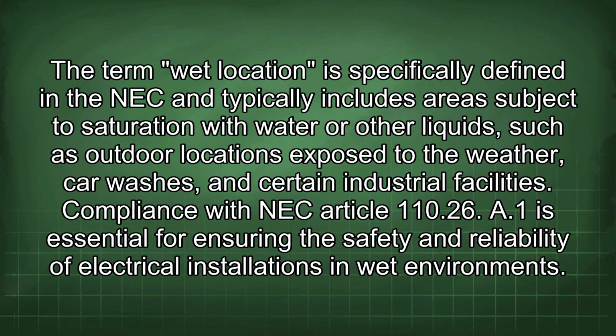The term wet location is specifically defined in the NEC and typically includes areas subject to saturation with water or other liquids, such as outdoor locations exposed to the weather, car washes, and certain industrial facilities. Compliance with NEC Article 110.26.A1 is essential for ensuring the safety and reliability of electrical installations in wet environments.